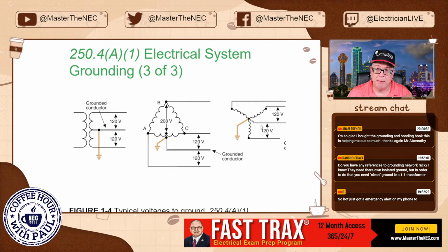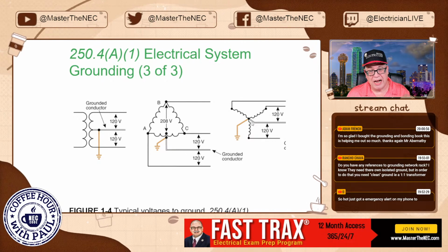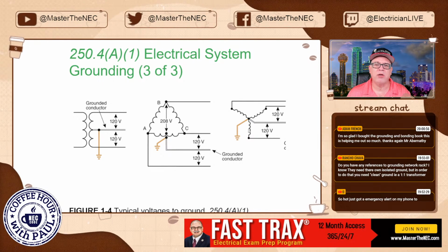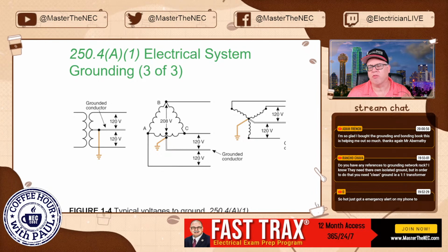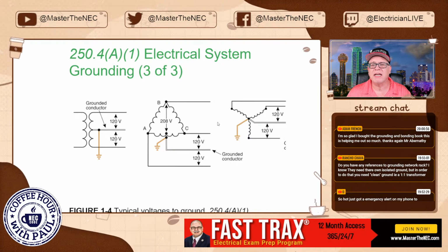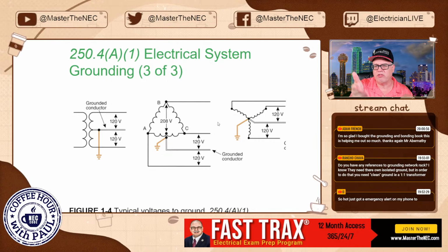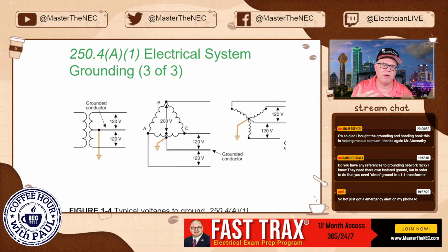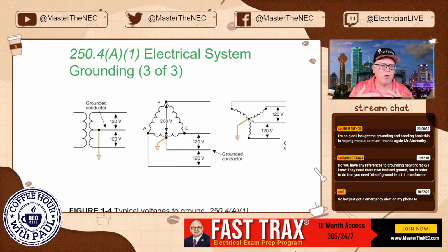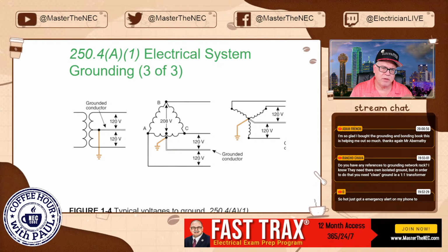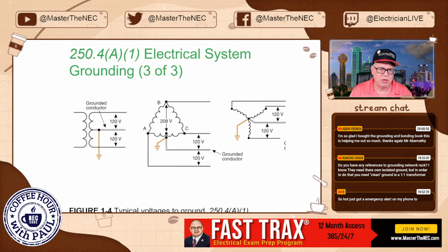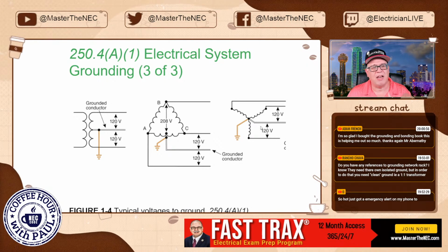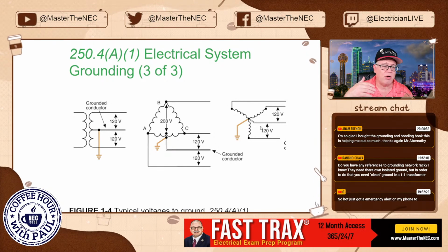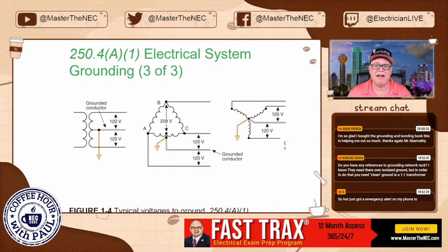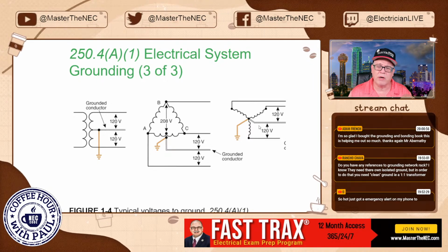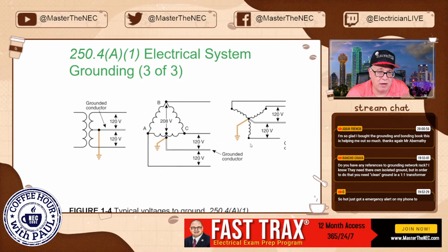Same thing over here, but this is a Y. So in this Y, people ask why you would use a delta over a Y. I get this question a lot. Let's say it's not this 120/208 delta, but say it's a 240 volt delta or whatnot. You can get more phase-to-phase loads out of it, so you might have less lighting loads, less receptacle loads. But a lot of times, office buildings that have a lot of 120 volt loads, they like to use the Y because you have a lot more ability to get 120 volt loads. It's irrelevant to our conversation.